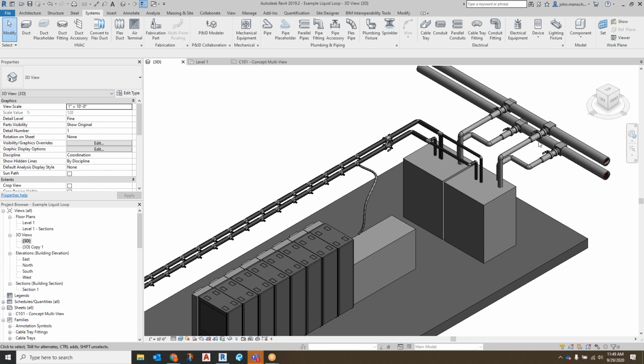I was just in general saying, if we need to give somebody guidance as to how much KW they can pull off of a given pipe size based on a given delta T, that's a helpful number. They know they've got 5-inch tap offs on their chilled water, they don't know what that means. They know it's 5 inches, they maybe can figure out the GPM, but they're not going to know what it means for KW. That was the intent I came up with.